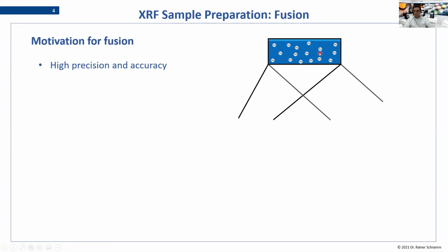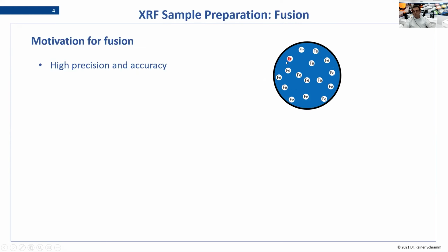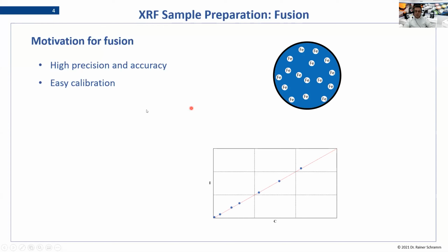But it's not only in the depth of the sample, it's also on the surface where we need a homogeneous distribution. Only then will we get high precision. The other big motivation is the ease of calibration in fusion. We can either use certified reference material and dissolve it into glass, and because of the dilution, most calibrations are not so curved, as we know from press pellets. So we don't need as much matrix correction as in press pellets. This is one advantage.